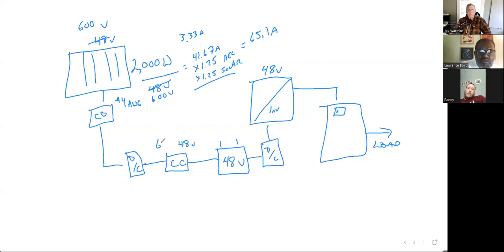With an MPPT charge controller, the voltage can come in at 600 volts but leaves at 48 volts. That's what an MPPT charge controller does. You've got to have a charge controller on a standalone system. On a grid-tied system, there are no batteries - you don't need the charge controller, it's going straight to the inverter.